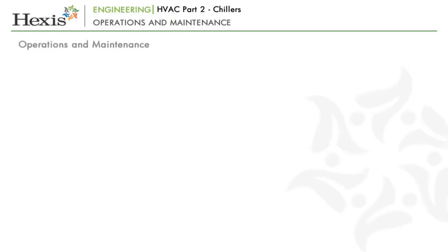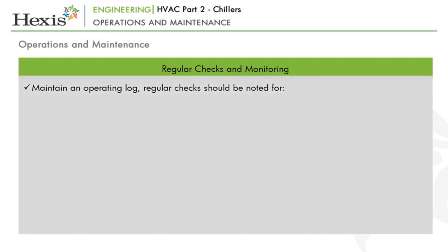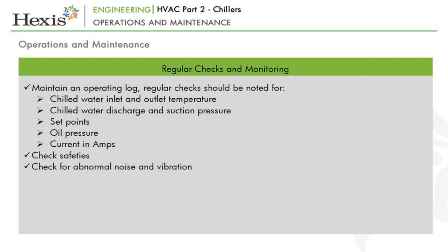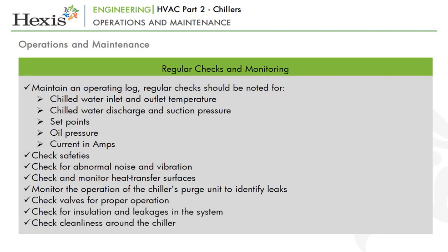Let us now learn about the operations and maintenance of chillers. All chillers require continuous maintenance for proper functioning. Regular checks and monitoring should include: maintaining an operating log; recording chilled water inlet and outlet temperature; chilled water discharge and suction pressure; set points; oil pressure; current in amperes; and safeties such as high pressure or low pressure cutout, oil pressure cutouts, and phase reversal protection. The operations of these safeties need to be checked. Also check for abnormal noise and vibration in the chiller, keep heat transfer surfaces clean, monitor the chiller's purge unit to identify leaks, check valves for proper operation, check for insulation and leakages, and check cleanliness around the chiller.